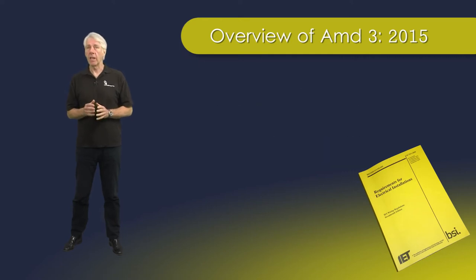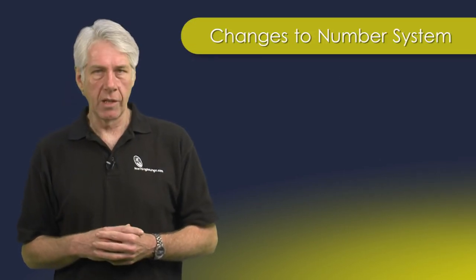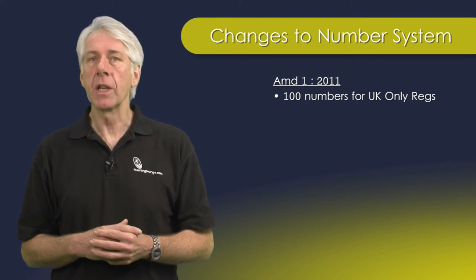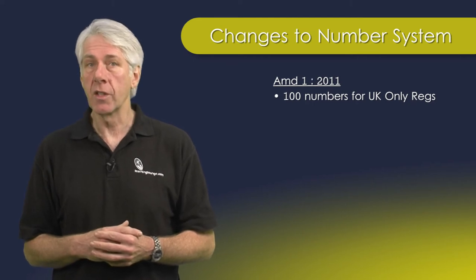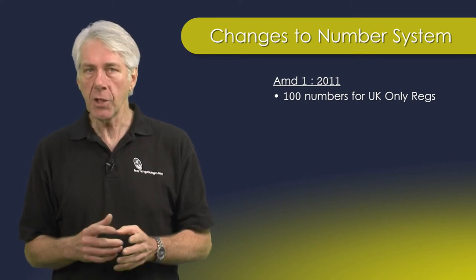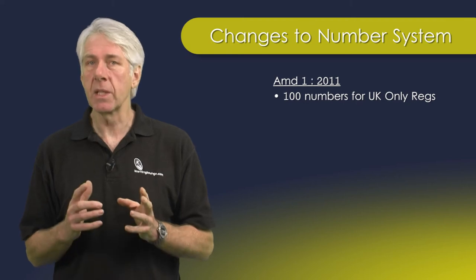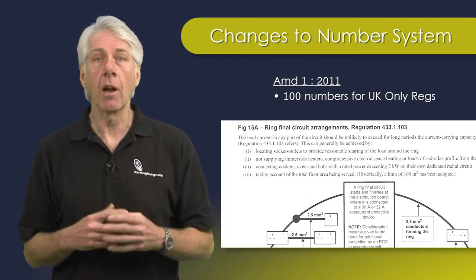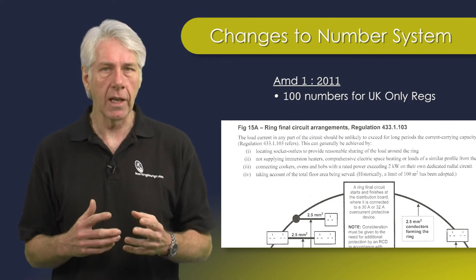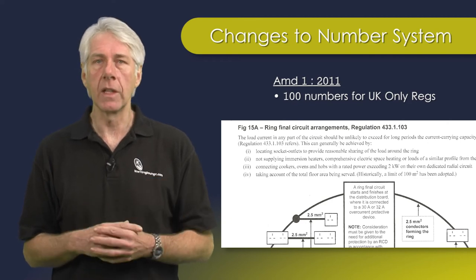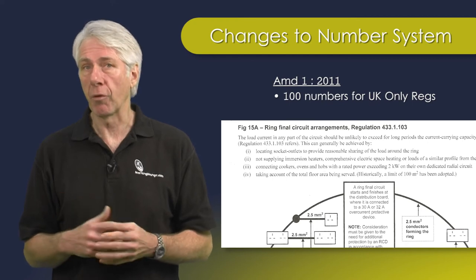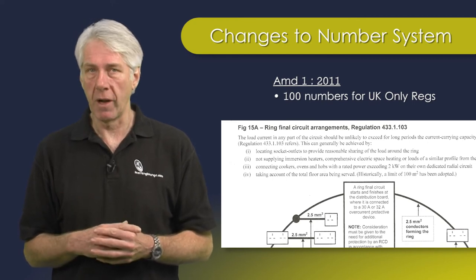Let's first take a look at a tweak to the number system. When Amendment 1 was introduced in 2011, some regulation numbers were altered to have numbers in the hundreds inserted at the end. This was to highlight regulations that were specific to the UK, so for example any regulation concerning ring final circuits, which are primarily used in the UK, would have a 100 at the end — for example, 433.1.103.